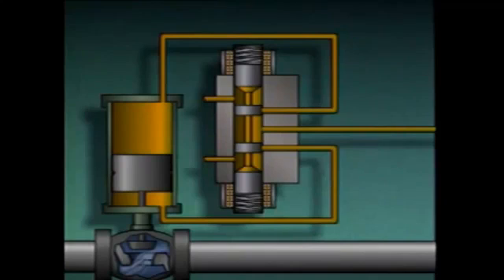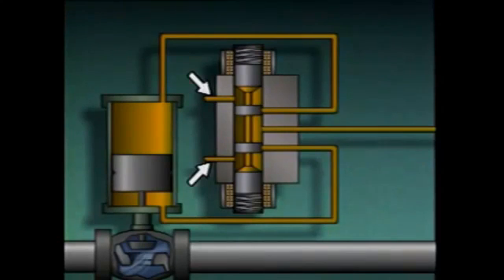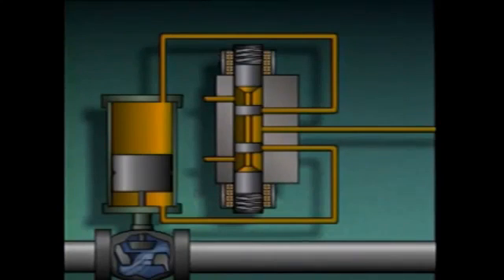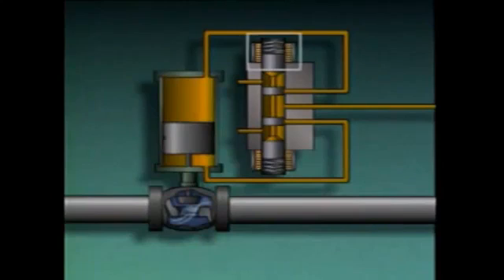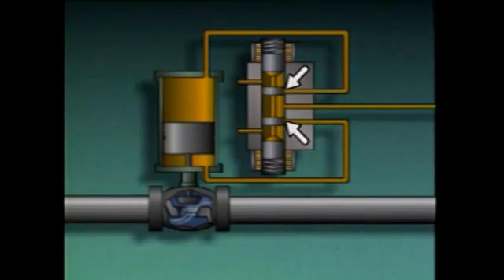A pilot valve consists of a valve body, two solenoids, a spool, a spring at each end of the spool, a hydraulic fluid supply port, two hydraulic fluid ports to the actuator, and two hydraulic fluid vent ports. The pilot valve is operated by the solenoids — electrical coils that respond to signals from a controller to position the spool. When both solenoids are de-energized, the springs return the spool to a neutral or centered position, blocking the fluid lines to the actuator cylinder and holding the actuator's piston in place.